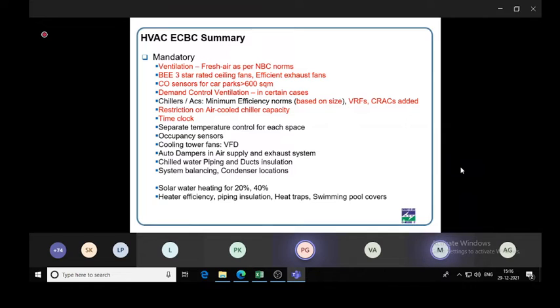In the HVAC section, we have these mandatory ones, the ventilation, the minimum fresh air should be there. We should have BEE 3-star rated fans and efficient exhaust fans. And parking spaces, if we have basement parking more than 600 square meters, then CO sensors are mandatory. Demand control ventilation, this is mandatory in certain situations. Minimum efficiency for the equipment like chillers, VRF, computer room air conditioner.